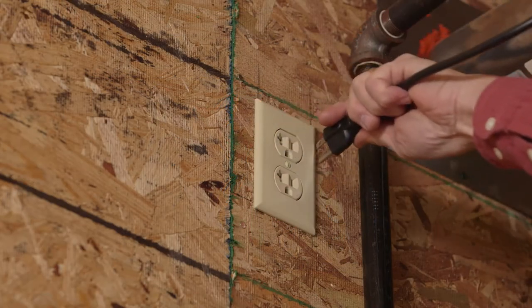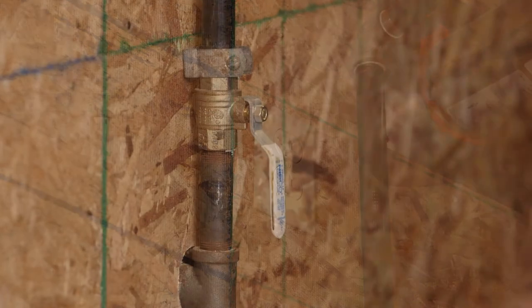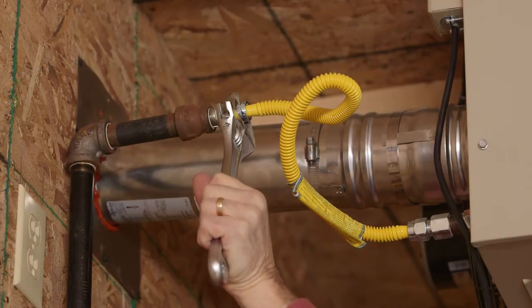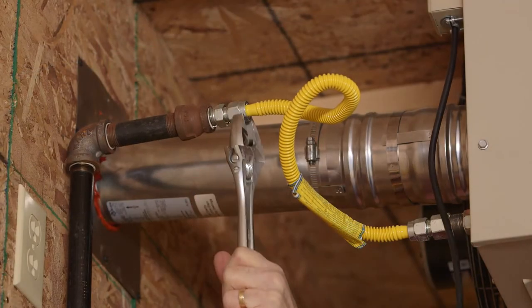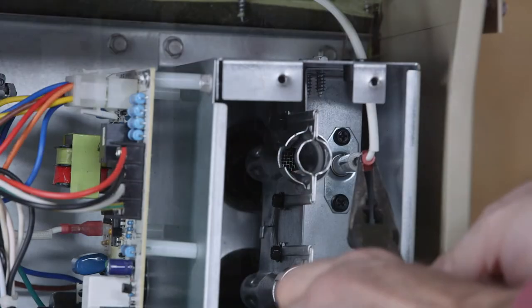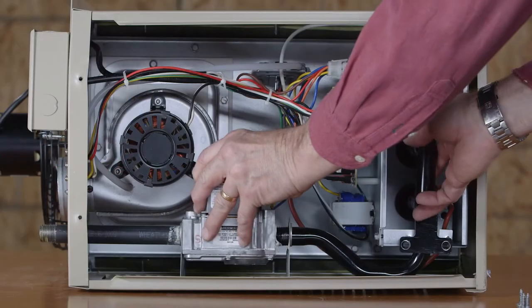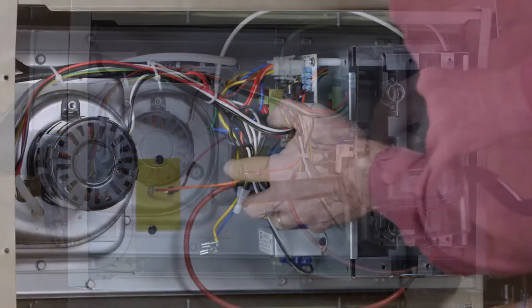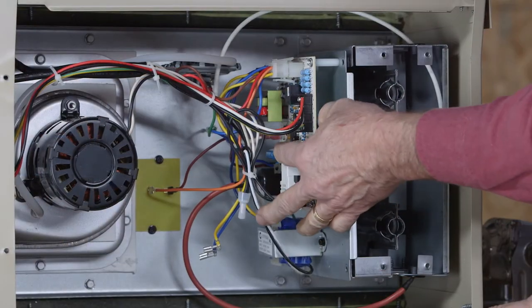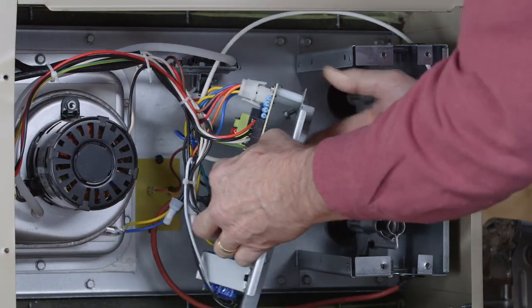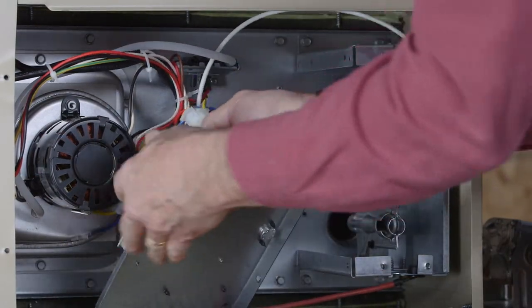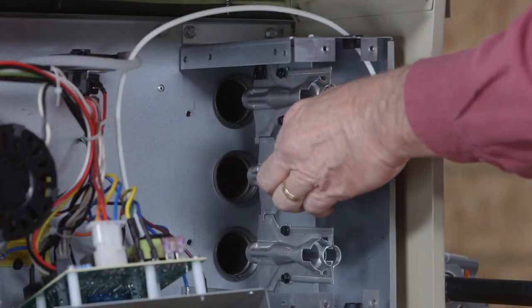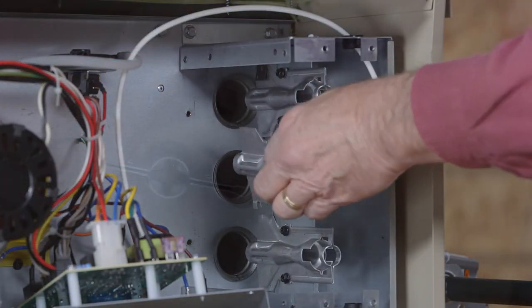To clean burners, turn off electrical gas supplies. Disconnect gas supply piping, high tension, and sensor leads. Remove the gas manifold, then remove the panel that the circuit board bolts to to get access to the burners. Clean burners as necessary.